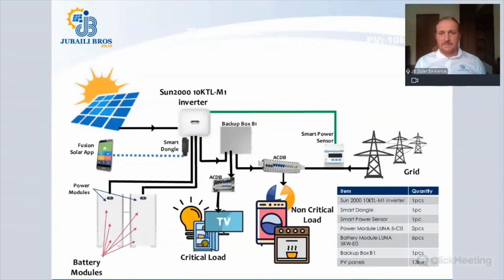I hope that makes sense, that's a very key point to keep in mind. So the Luna is a great application in the case of, number one, a single phase scenario - it works great. Number two, a 3-phase scenario with a stable grid - if the grid is stable, this is a great 3-phase solution. If the grid is not stable and you have a 3-phase installation, whenever the grid fails, your Luna will only provide power on a single phase to the critical loads.